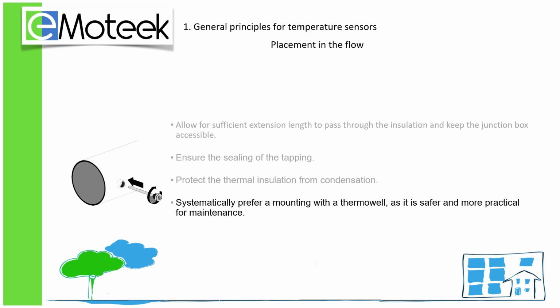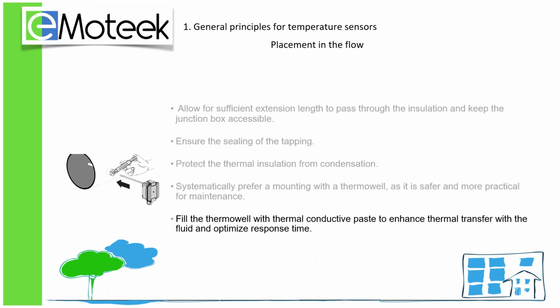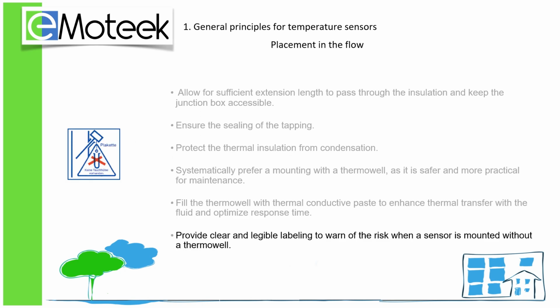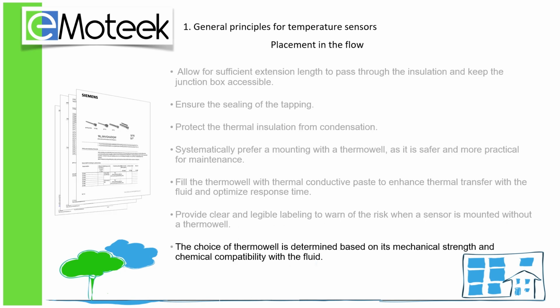Oh, I see. Fill the thermowell with thermal conductive paste to enhance thermal exchange with the fluid and optimize the response time. Make a clear and readable marking to warn of the risk when a sensor is mounted without a thermowell. The choice of the thermowell depends on its mechanical strength and compatibility with the fluid. So I can't use the same thermowell for all my installations? That's right. It will depend on the fluid present in the installation and the type of installation.